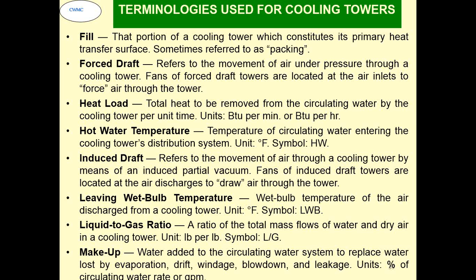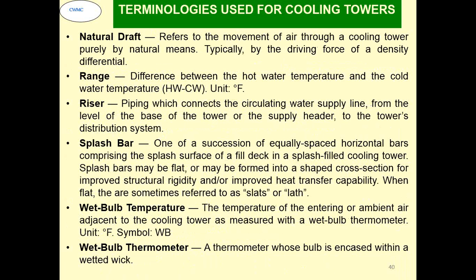Liquid to gas ratio is the ratio of the total mass flow of water and dry air in a cooling tower. Units are LB or kg per kg. Makeup is the water which is added to the circulating water system to replace water which is lost by evaporation, drift, windage, blowdown or leakages. These are measured in terms of the percentage of circulation water, and units are generally meter cube per hour. Natural draft. This refers to the movement of air through a cooling tower purely by natural means, typically by driving force of a density differential. Range is the difference between the hot water temperature and the cold water temperature. The units are degree Fahrenheit or degree centigrade.